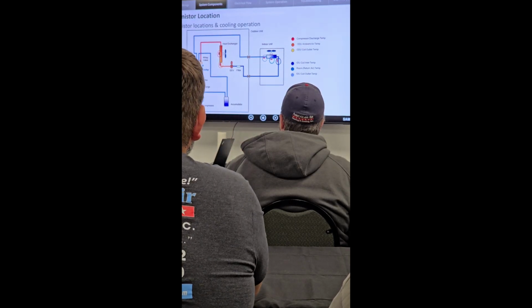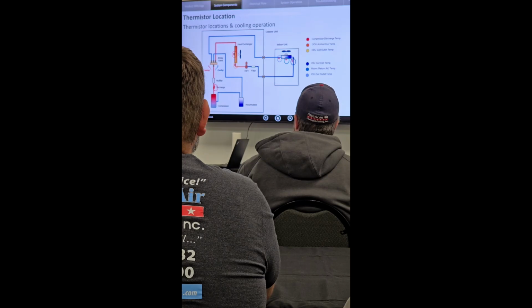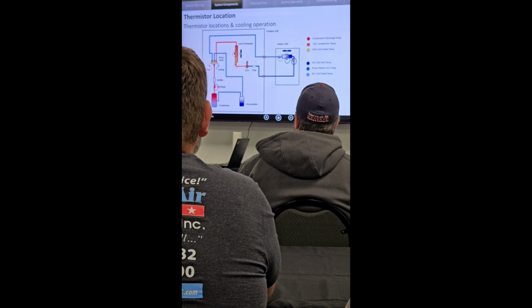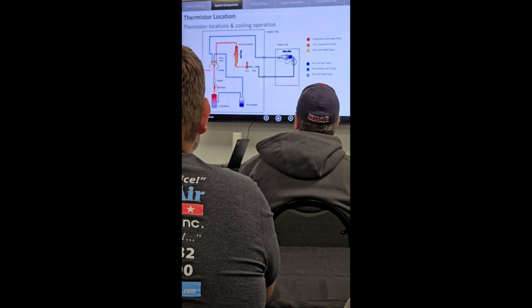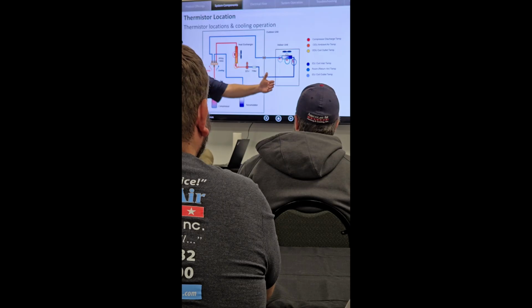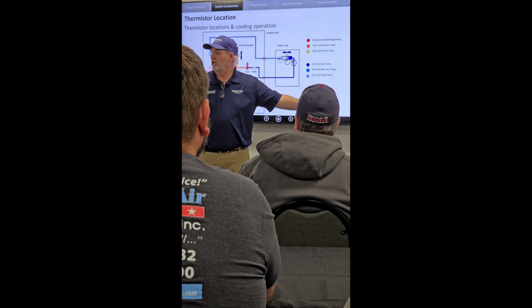So have we had that? Yes sir. We run it in heat cycle for about 10, 15 minutes, clears it up, it'll run good for about another month, and then it becomes an oil loop trap issue again. So yes, do not take more than one loop, that's it. Just one loop, and make it as big as the back side of the unit, if that makes sense. You should be able to hide it.